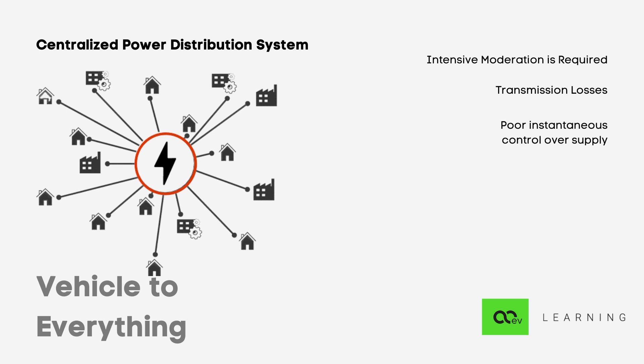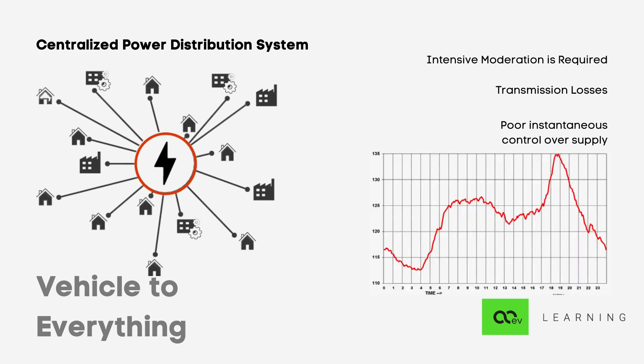All the traditional sources listed are not capable of scaling up or scaling down instantaneously as per demand fluctuation. Like a 20 megawatt thermal power plant running on coal cannot instantaneously supply 25 megawatt in the evening when we all switch on our lights together, or reduce to 10 megawatt in the afternoon when industrial and residential activity is lowest. Similarly, a hydropower plant also cannot increase or decrease its capacity based on demand. As per the Indian daily electricity demand curve, energy consumption rises from 6 AM and peaks around 11 AM, then drops during afternoon hours and rises again in the evening due to use of lights, air conditioning, and systems as people get home from office.